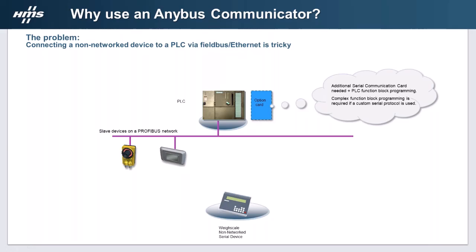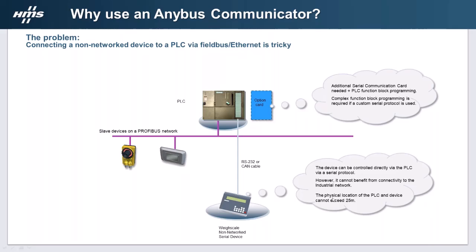You can put an option card on the PLC, and that does work — for some circumstances it works really well. But the problem is it can sometimes be really expensive, and it also requires a lot of programming, which requires some kind of specialist technology. Another option is to directly connect it to the PLC, which is normally a bit quicker. But the problem with that is it's only connected to the PLC itself — it's not actually on the network. The whole principle of networking is that all the machines can talk to each other and share information, so connecting only to the PLC defeats the purpose.